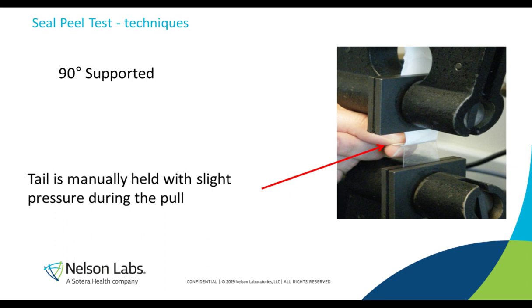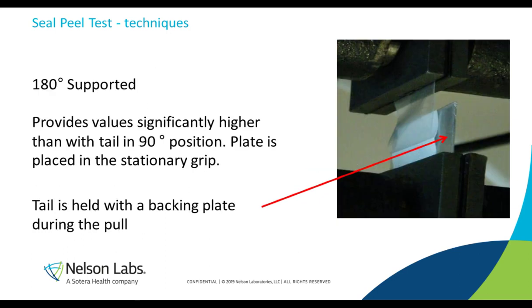This option is the 90-degree supported. It is done by using your fingers to hold the tail. It's very important that when you're performing this method, you are guiding the tail and not actually pinching it, because you will change the results when you're following this method. This method is the recommended method listed in the EN 868-5 for peelable pouches, and it actually does have a recommended minimum seal strength in there, just as an informational.